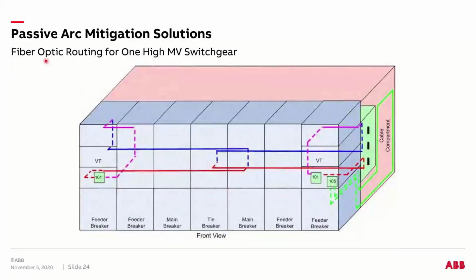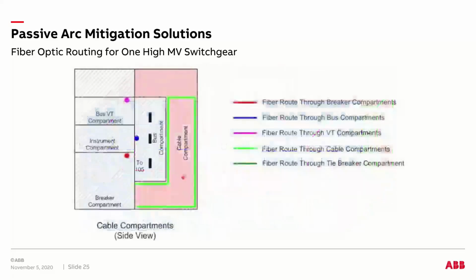So these are some of the examples of how we do the fiber routing within the medium voltage switchgear. The red signifies the fiber optic cable going through the breakers, and the violet is going through the transformers, the voltage and bus PT and line PT, and the green is the cable going through your cable compartment, and then you have the blue that is going through your main bus compartment. So it kind of shows right here on the cross-sectional view. So we have the green area, we have the red, we have the blue, as well as the violet.